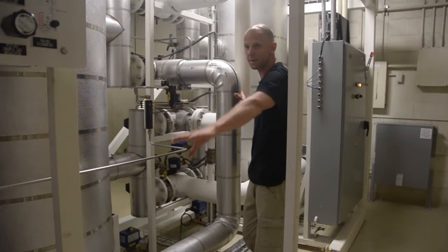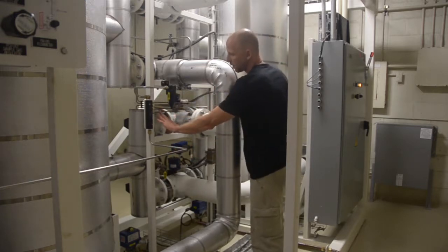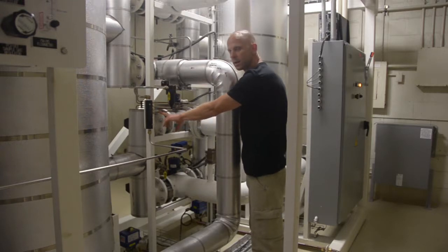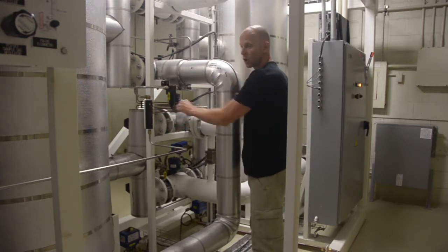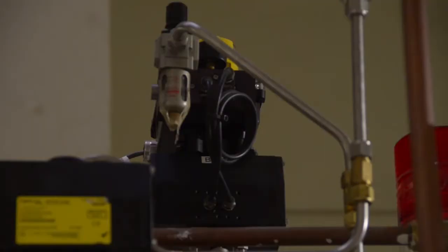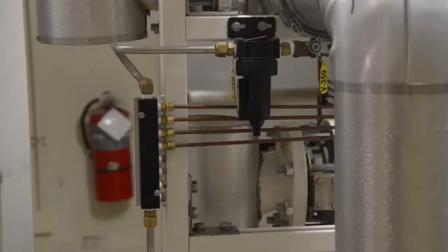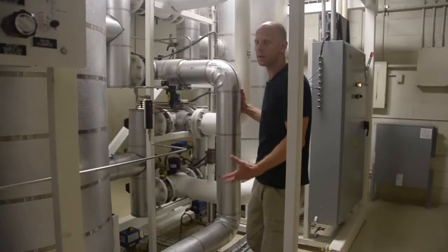So some of it will go to seal gas for the turbine. Some of these 4 lines are going to our main process bed valves, which are pneumatically powered. Our main trip valve is also pneumatically powered. So this manifold distributes. There's a secondary manifold as well, and from there it's distributed to wherever instrument air is needed.